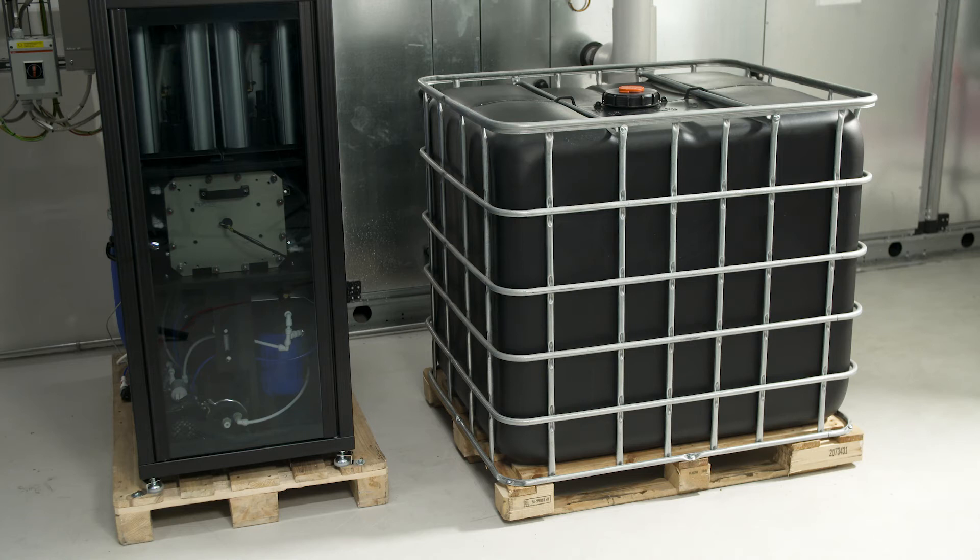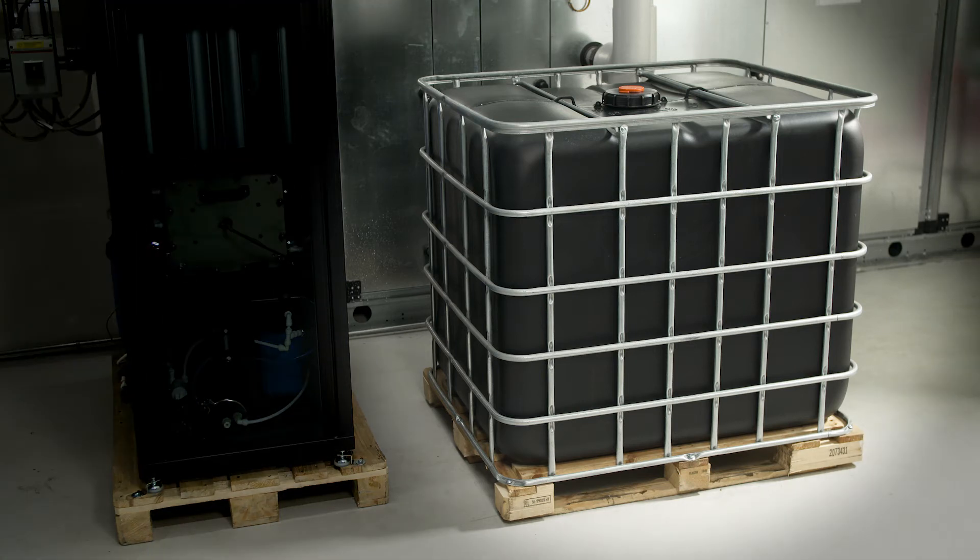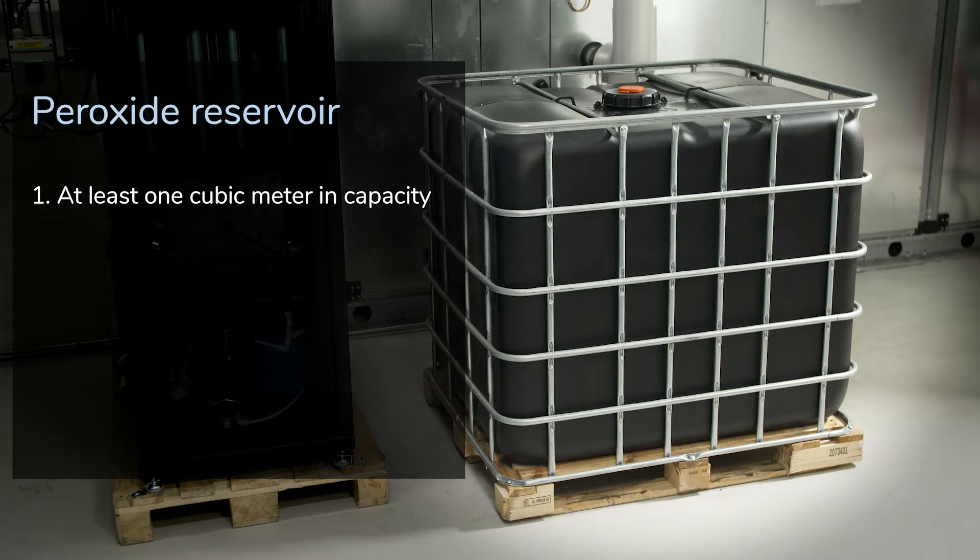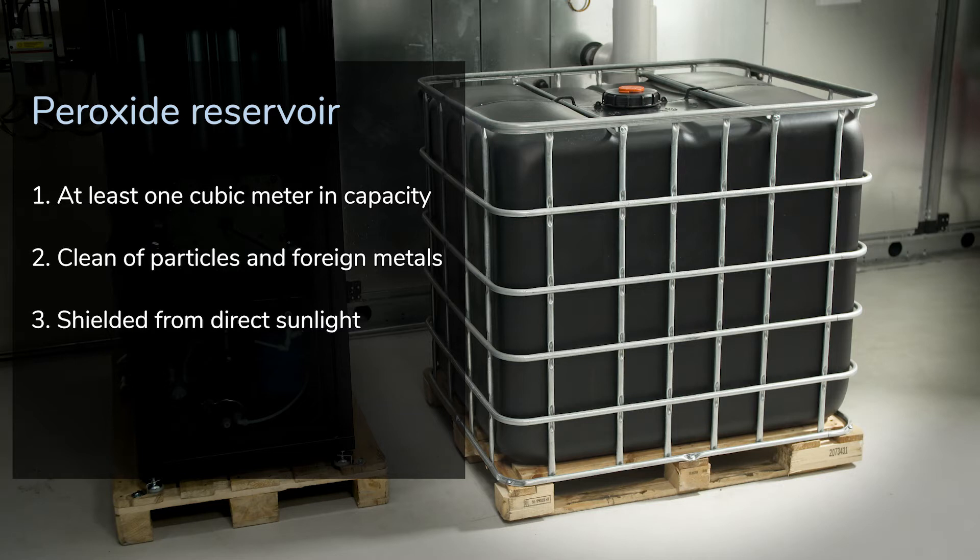Let us start with preparing the peroxide reservoir in three steps. It should have at least one cubic meter in capacity, be clean of particles and foreign metals, and it should be shielded from direct sunlight. The container walls should be of dark color with no openings for dust and metals.